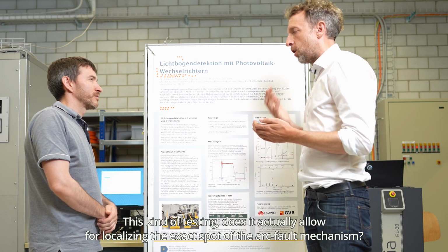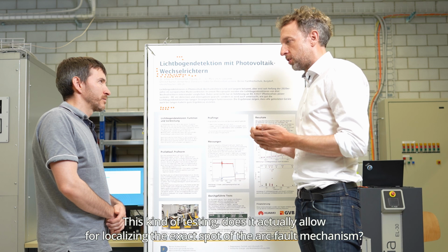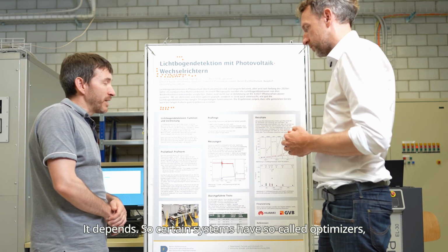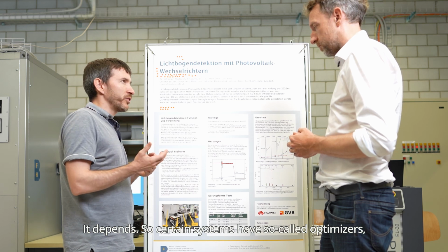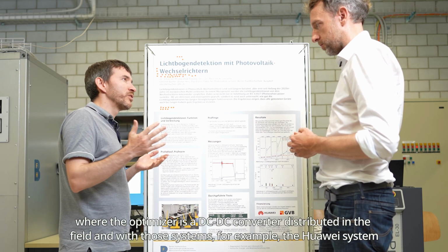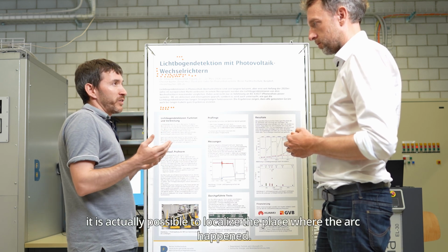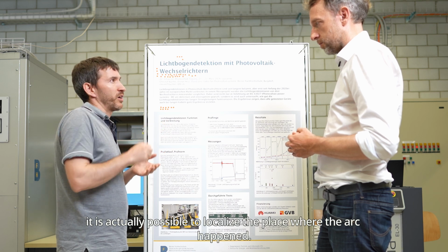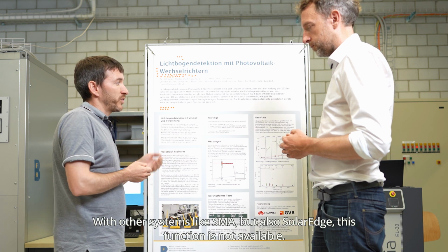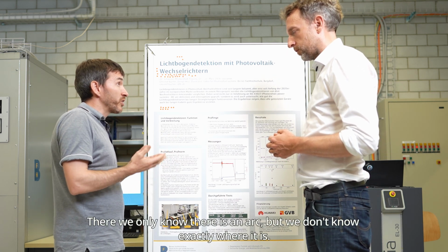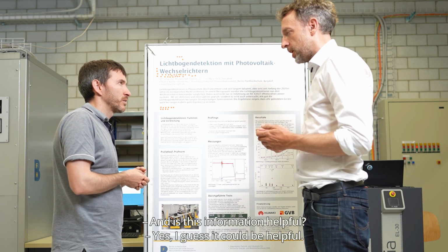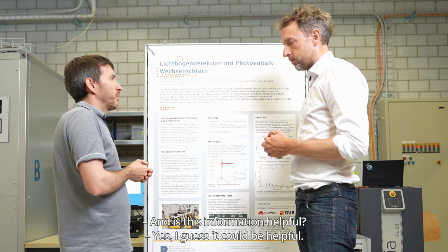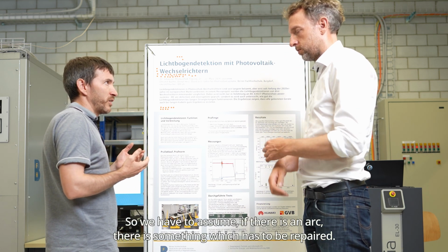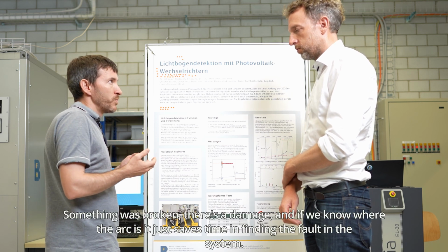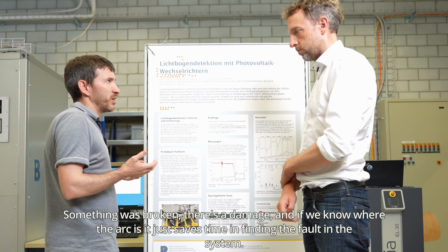This kind of testing, does it actually allow for localizing the exact spot of the arc fault? It depends. So certain systems that have so-called optimizers, where the optimizer is a DC-DC converter distributed in the field. And with those systems, for example, the Huawei system, it is actually possible to localize the place where the arc happened. With other systems, like SMA, but also SolarEdge, this function is not available. There, we only know there is an arc, but we don't know exactly where it is. And is this information helpful? Yes, I guess it could be helpful. So we have to assume if there is an arc, there is something which has to be repaired. Something was broken, there's a damage. And if we know where the arc is, it just saves time in finding the fault in the system.